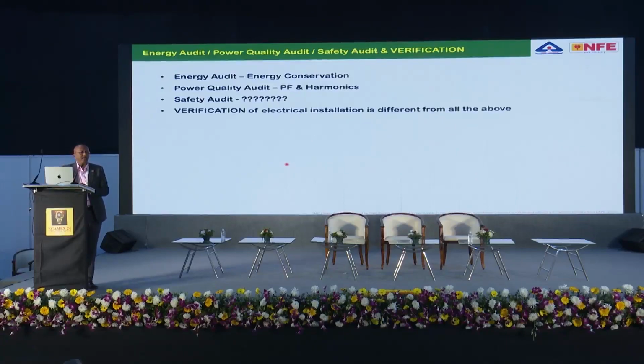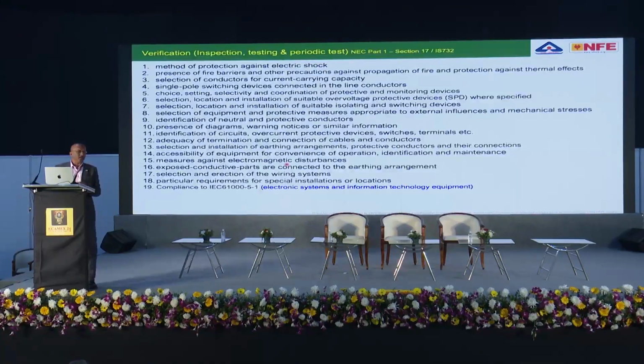So we didn't use the word audit in our standards. We use the word verification, because audit is a subject where, imagine you have 100 circuits, you test 10 circuits and you imagine that the remaining 90 are in good condition. That is audit. Here in verification, we are talking about safety. If there is no safety, a building can catch fire or people will die. Every circuit you should do. So you should verify. Verification consists of inspection. There are several subjects of inspection.